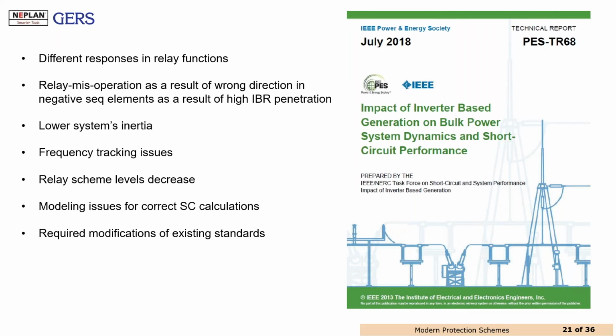Another publication that we have is the impact of inverter-based generation on the bulk power system, and that is mainly related to the short circuit contributions, because maybe you remember the waveform of the current that I presented before. But we have different challenges because of the impact of these kinds of systems. They cause, for example, different responses in the relays, misoperation because of the improper direction of the negative sequence elements due to the high penetration of these kinds of systems, the lower system inertia, the frequency issues, the short circuit levels.